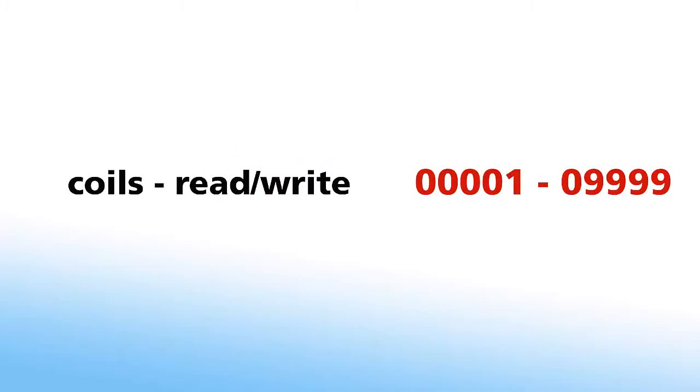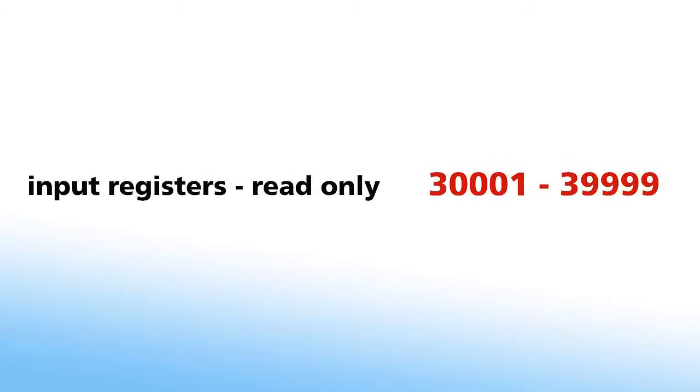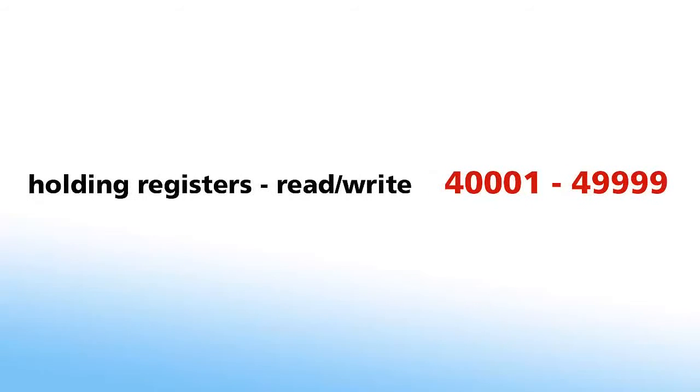Data table addresses 1 through 9,999 are the read-write table for coils. Addresses 10,001 through 19,999 are the read-only for discrete inputs. Data table addresses 30,001 through 39,999 are the read-only for input registers, and addresses 40,001 through 49,999 are the read-write table for holding registers.